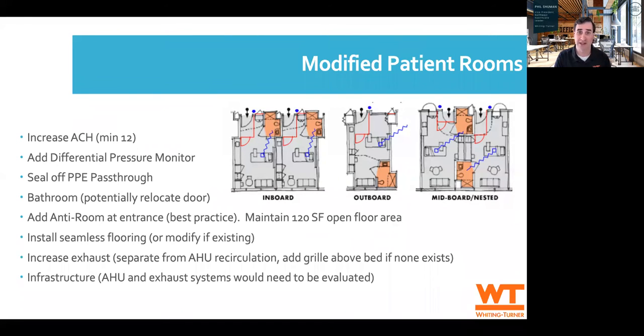Your bathroom, you need to take a look at specifically how it relates to any anteroom if you're going to be able to fit that in. But that bathroom door may need to be relocated if it doesn't work well with where the anteroom would be. If you are going to look at putting an anteroom in, you have to maintain 120 square feet within the patient room itself in order to meet the guideline requirements.